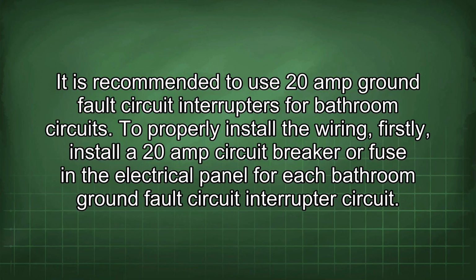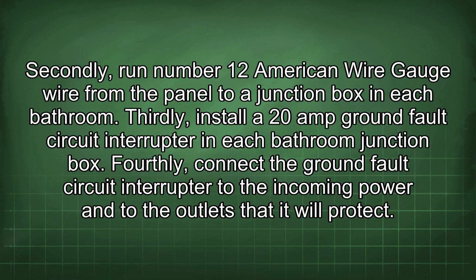To properly install the wiring, firstly, install a 20 amp circuit breaker or fuse in the electrical panel for each bathroom ground fault circuit interrupter circuit. Secondly, run number 12 American wire gauge wire from the panel to a junction box in each bathroom. Thirdly, install a 20 amp ground fault circuit interrupter in each bathroom junction box. Fourthly, connect the ground fault circuit interrupter to the incoming power and to the outlets that it will protect.